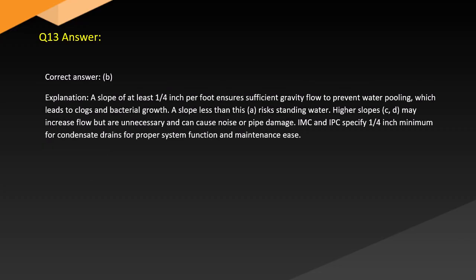Answer. Correct answer: B. Explanation: A slope of at least 1/4 inch per foot ensures sufficient gravity flow to prevent water pooling, which leads to clogs and bacterial growth. A slope less than this (A) risks standing water. Higher slopes (C, D) may increase flow but are unnecessary and can cause noise or pipe damage. The IMC and IPC specify 1/4 inch minimum for condensate drains for proper system function and maintenance.